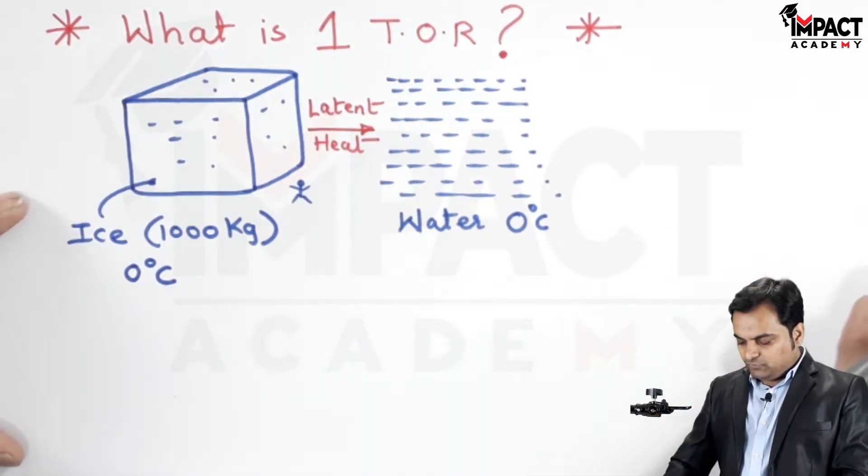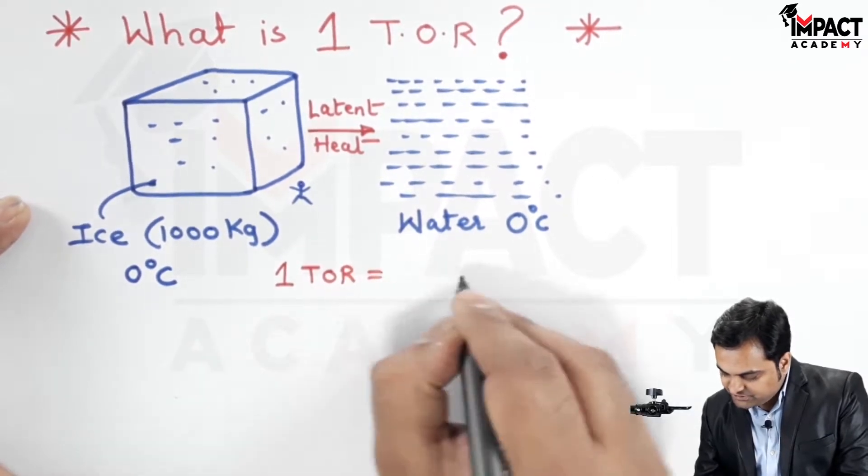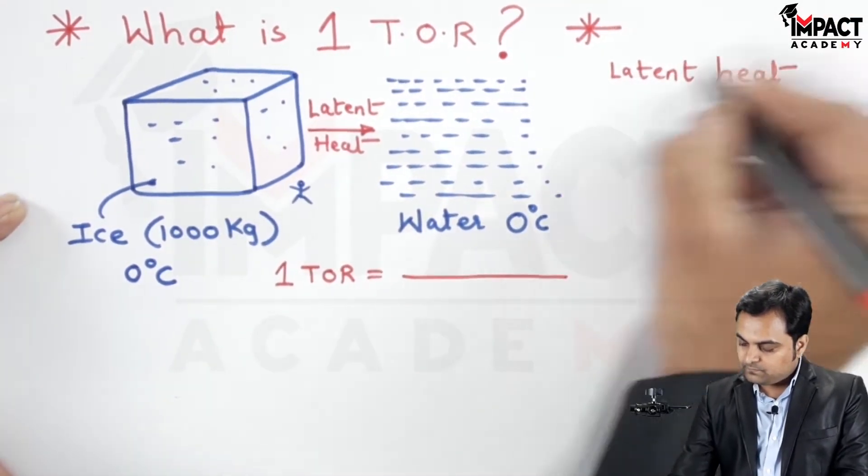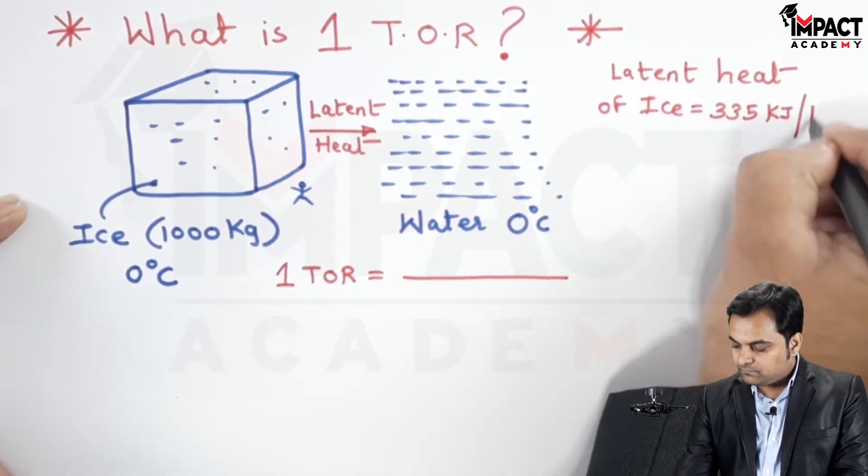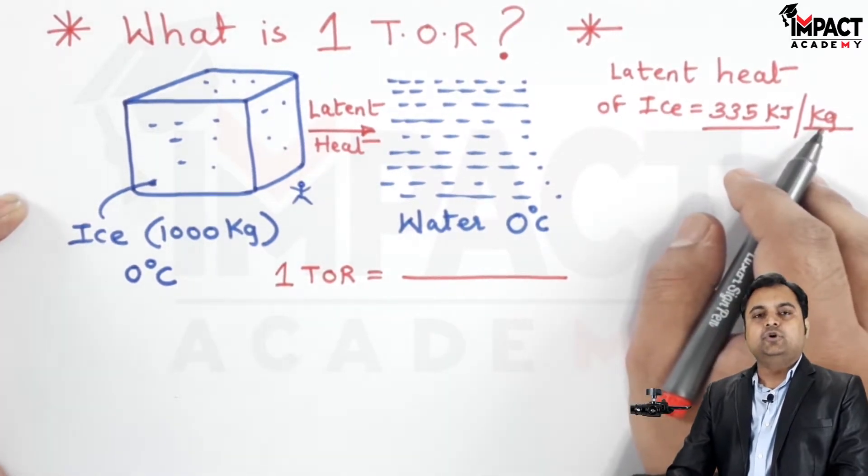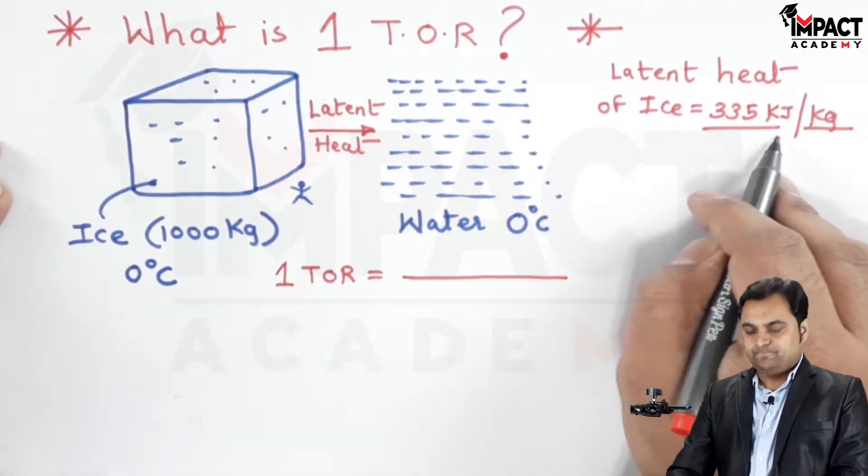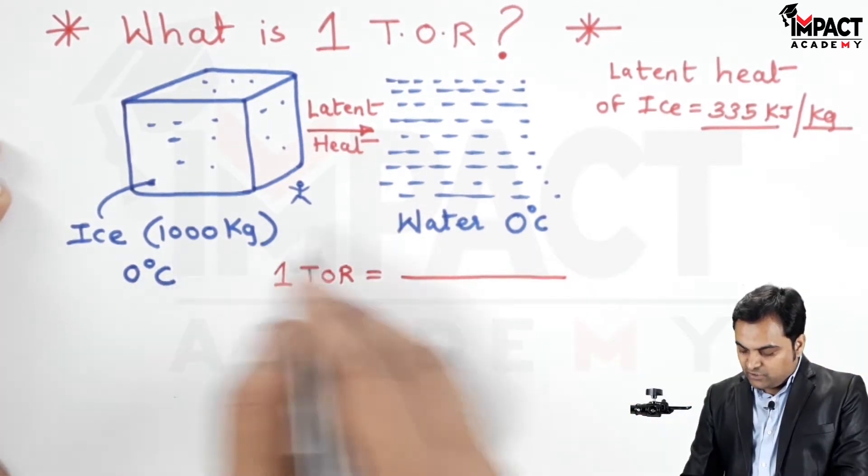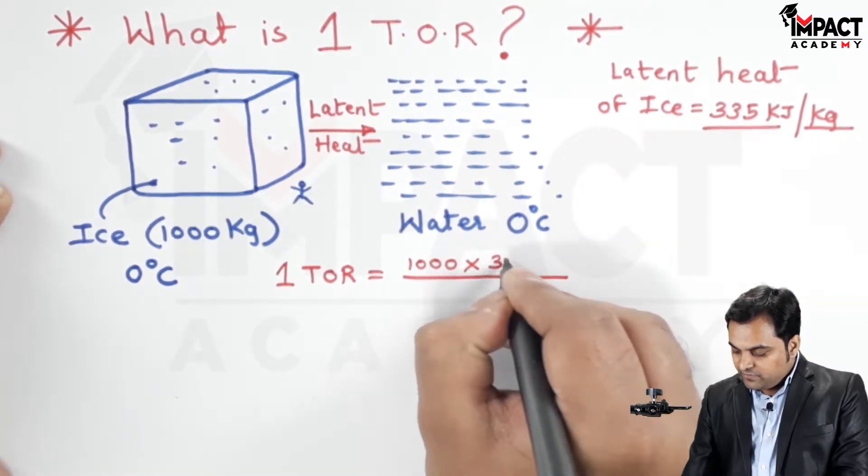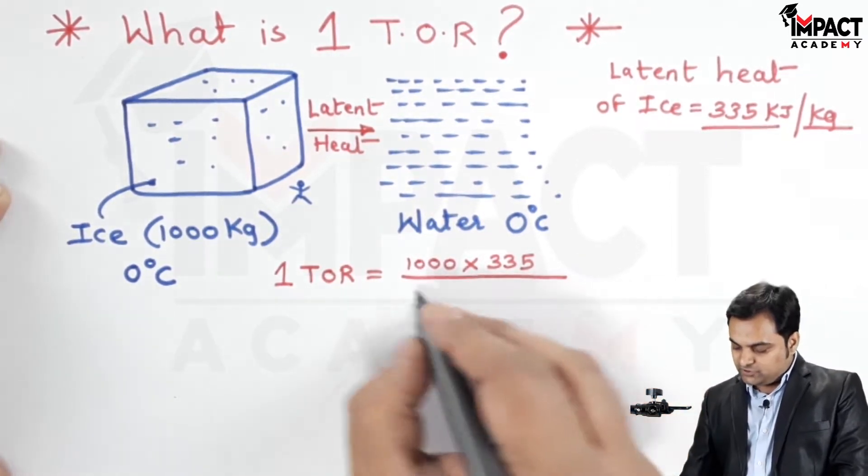It would be written this way: 1 ton of refrigeration equals... Now the latent heat of ice is 335 kilojoules per kg. It means for 1 kg of ice to convert into water, the heat which has to be supplied is 335 kilojoules. So for 1000 kg ice, it would be 1000 × 335 for the uniform melting of ice, and the time taken is 24 hours.